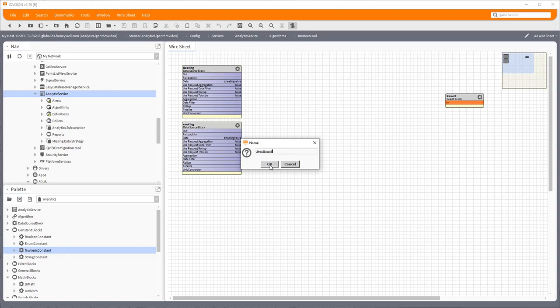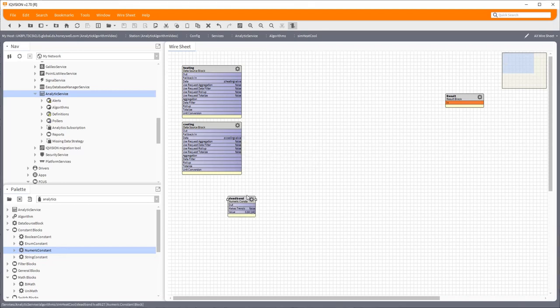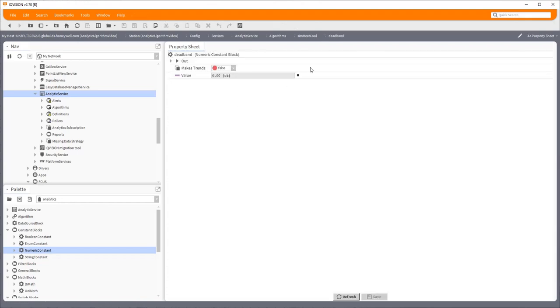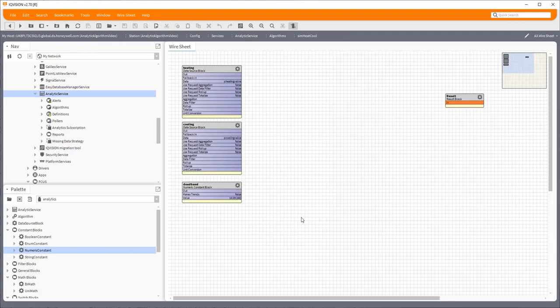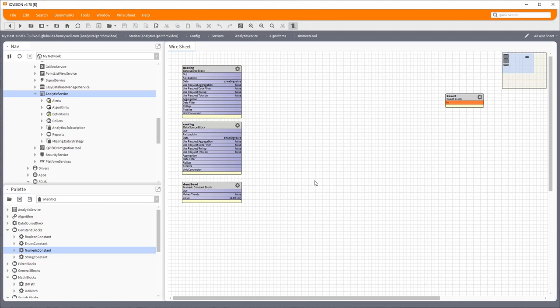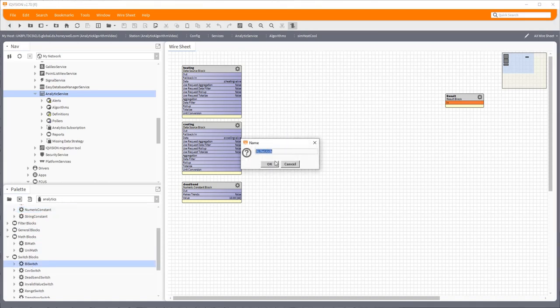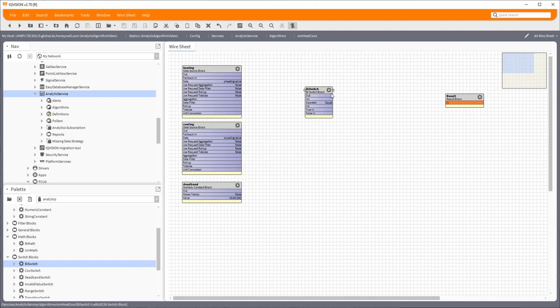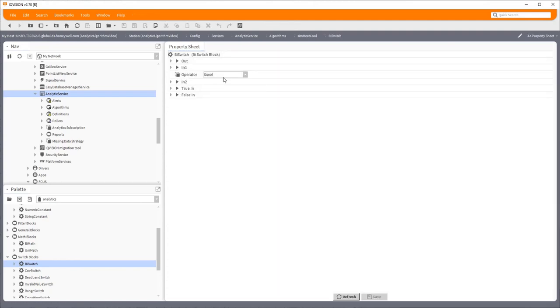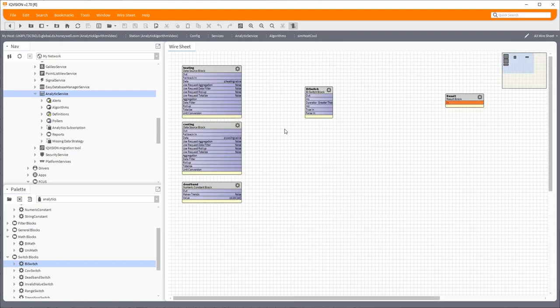The next thing I need is a constant. It's not really a deadband, but it will be anything that's between, so I want to know if both of those valves are open more than let's say 10 percent at any time. Now obviously there would be other perhaps mitigating factors when you do the algorithm, so for example frost protection and so on may actually legitimately demand these two things to be open, so you would need a more complicated algorithm than I'm using here. It's just this is a good example to start with. The next thing I want for my particular purpose here is a switch.